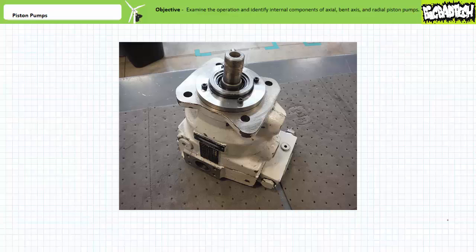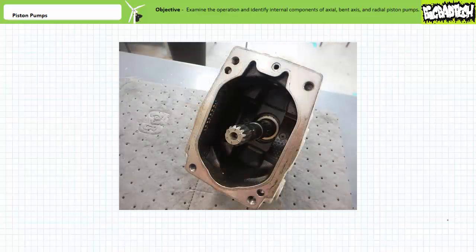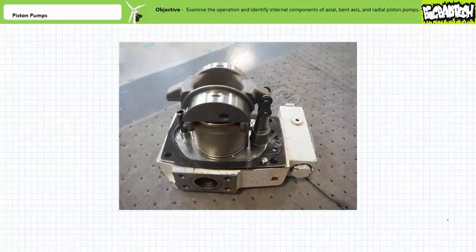That's about it for the basic internal construction and operation of piston pumps. Let's disassemble some axial piston pumps and see if we can identify some of the constituent parts. Here's an example of an axial piston pump. We can see the driveshaft, the housing or body, and some ports. When we pop off the top half of the housing, we can see the driveshaft and the valleys of a semicircular rocker mechanism into which the swashplate sits. Note the pump is missing a spring on one side of the swashplate.